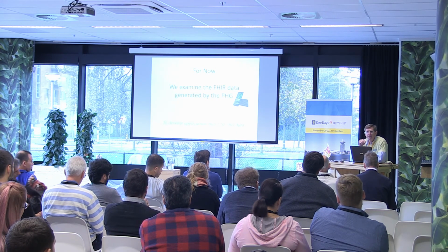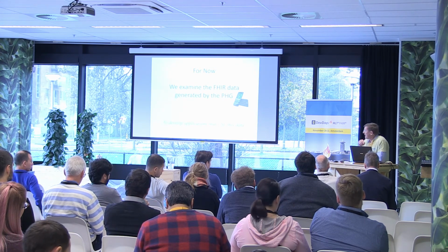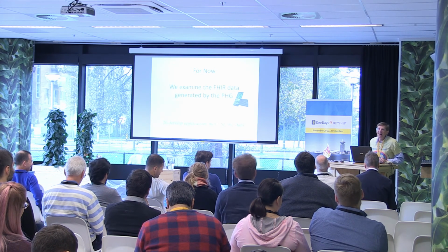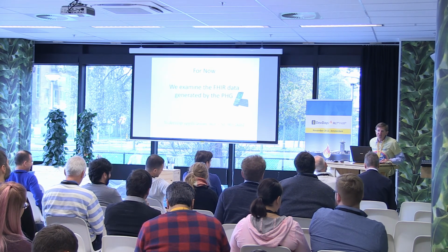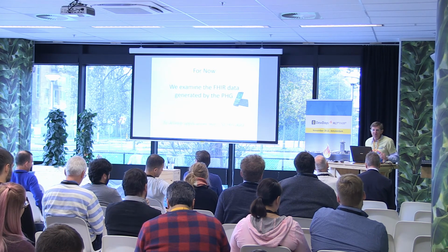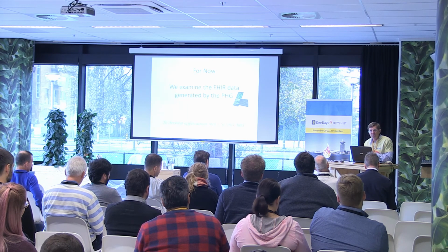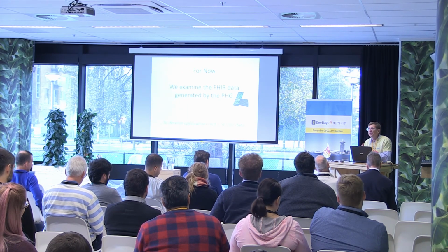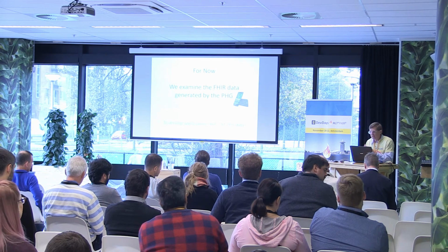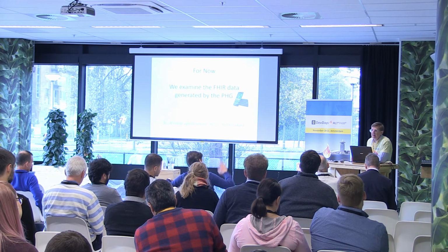You said there is no support for UDI in the devices, but your sample output also has a UDI. It's fake. It's all fake. It was doctored because we wanted to demonstrate that the device resource, which has the UDI, can do that. In fact, the UDI profile in FHIR had to be fixed, because there was no source that came from an electronic source. They had human input, or there were a few choices. But this is going to be electronic from the device, so we had to add that, and that has been added. That'll be in R5.